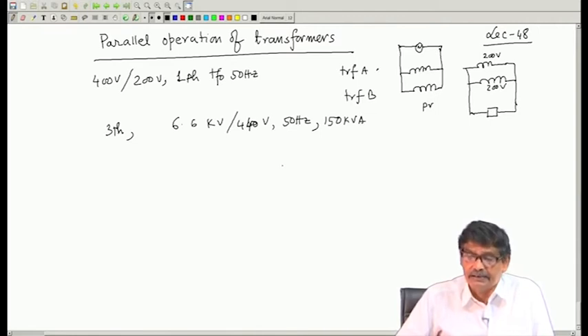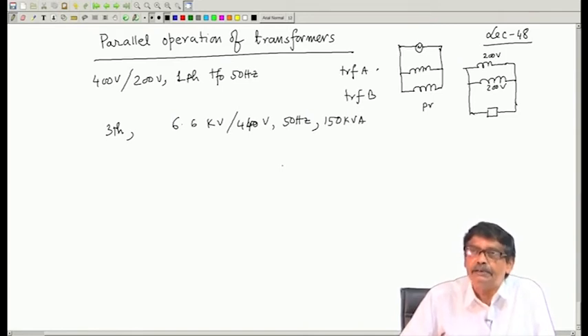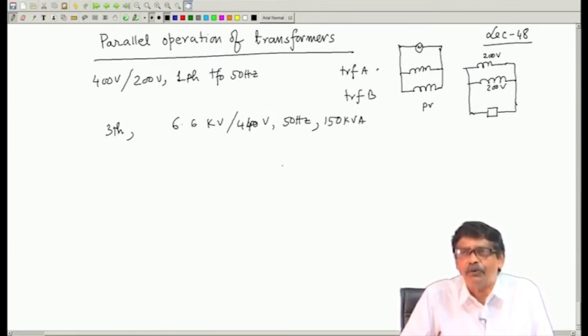Naturally, this transformer will now be insufficient, because if you want to deliver 300 kVA from this transformer which is rated at 150 kVA, it will be overloaded. See, kVA means current, mind you; the voltages are approximately the same. Even with the concept of regulation there will be slight voltage differences, but nonetheless the transformer will become overloaded. You cannot pass that current; kVA is synonymous with current, and voltages are almost the same.